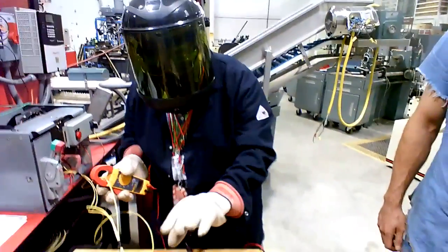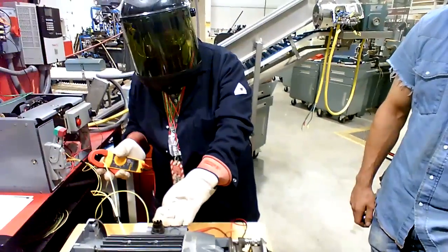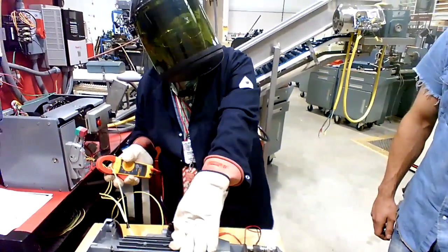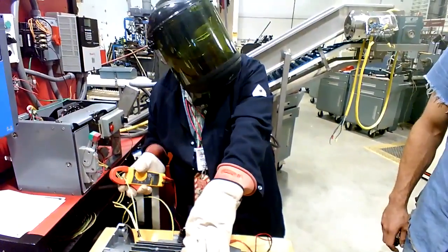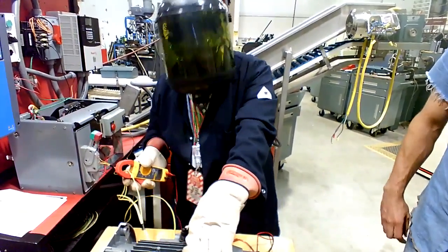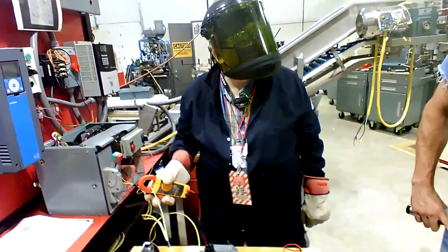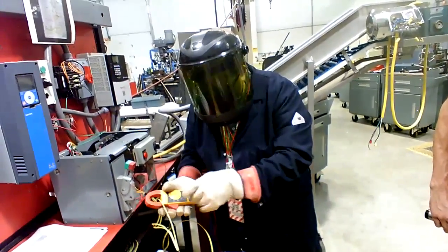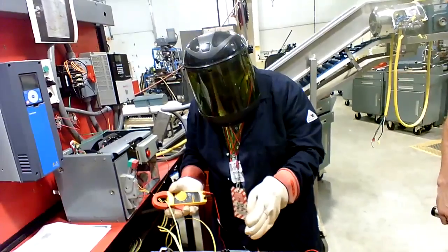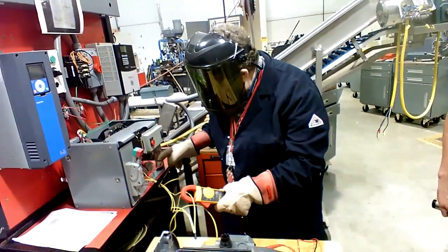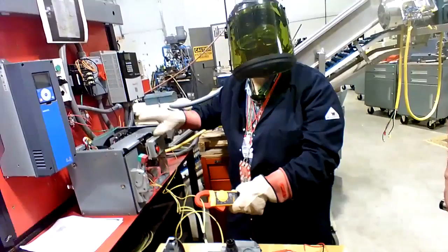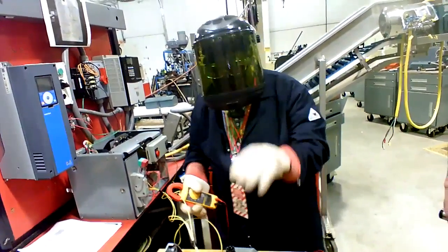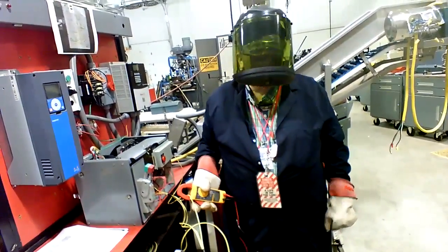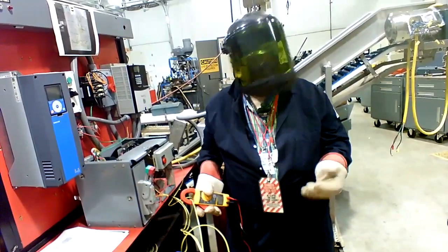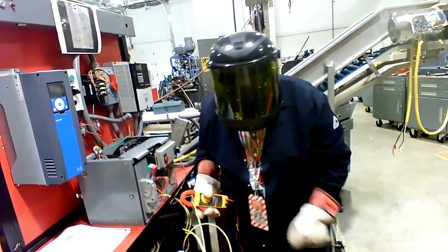Now, here's what you've got going on. You've got a resistance problem. There's something going on either with the connection in the peckerhead there, or you've got a winding that has some resistance problems. The windings don't have a balanced resistance in them. So when you see the amps not balanced, yet the voltages are, it has nothing to do with the bucket and voltage source. There's something wrong with the load. The load's not drawing a similar amount per leg, so it needs to be looked at, the motor itself.